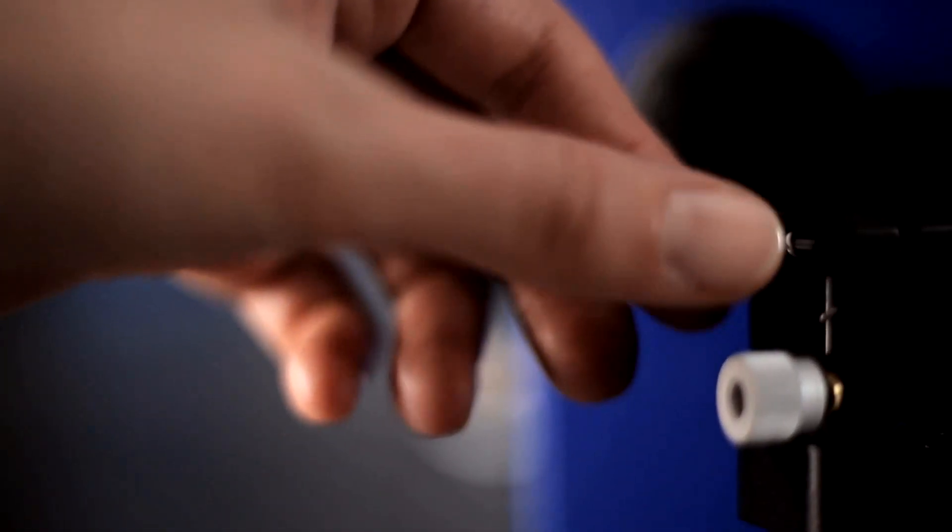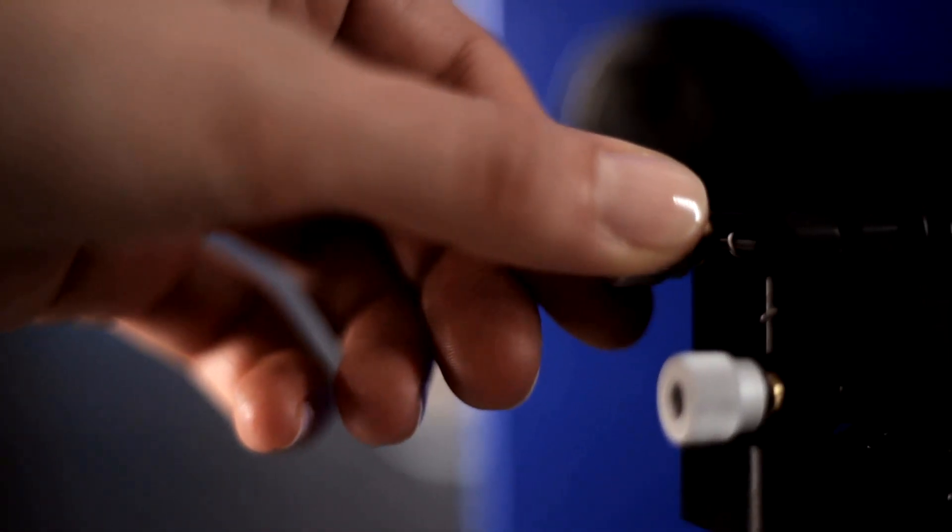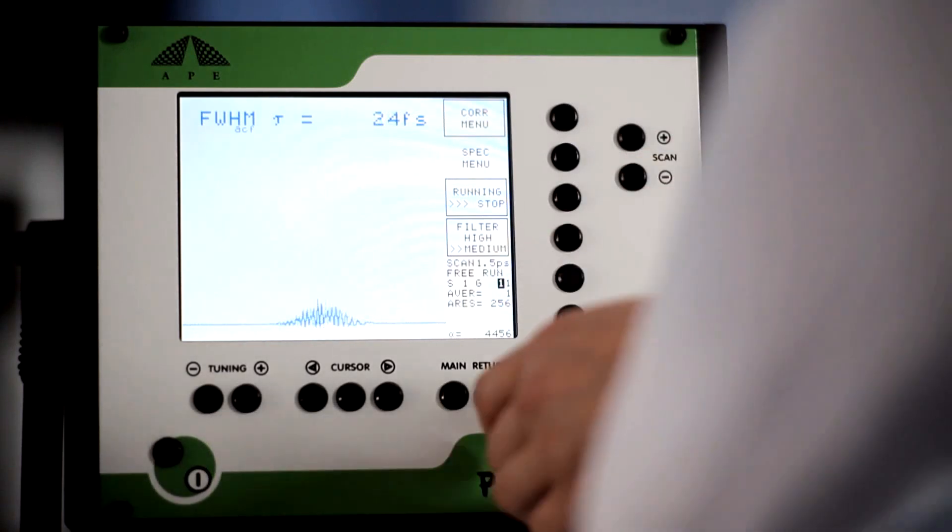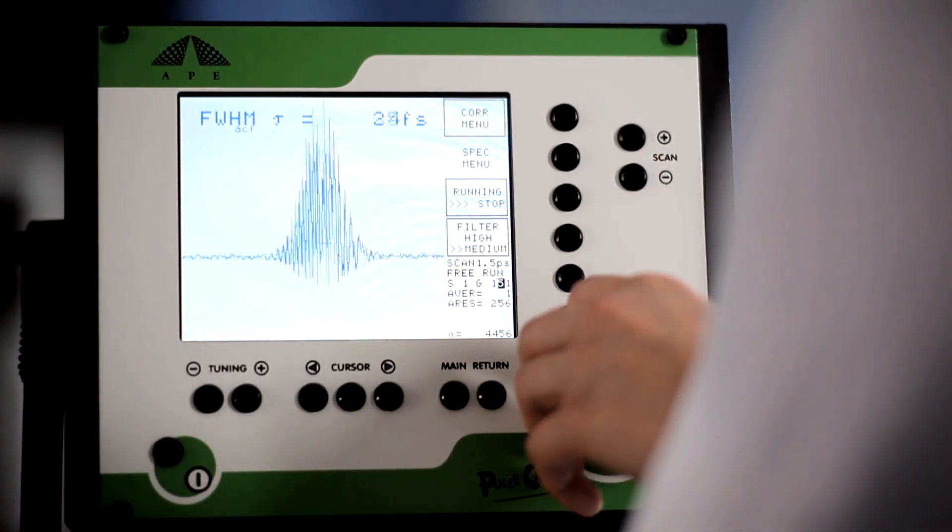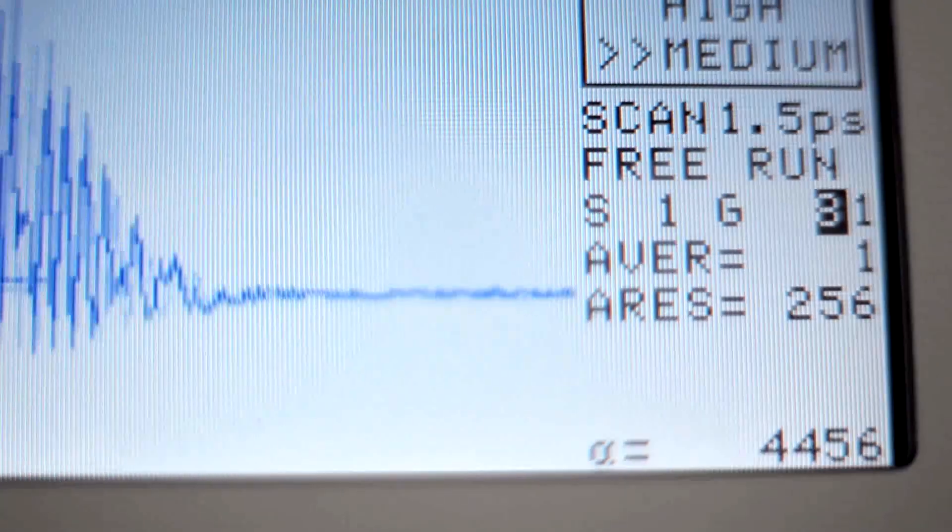To optimize the signal, gently turn the mirror screws. The controller screen should now display a measurement curve. If you only see a flat line, turn the gain dial to increase the signal. To see a measurement curve, your controller should also be set to free run mode.